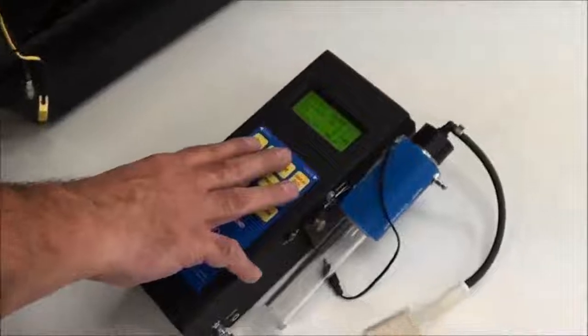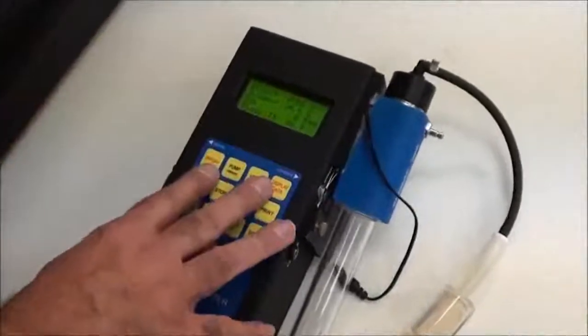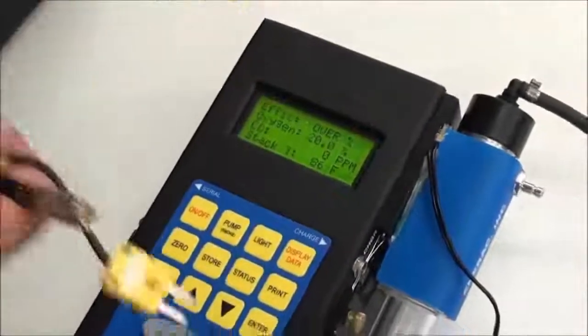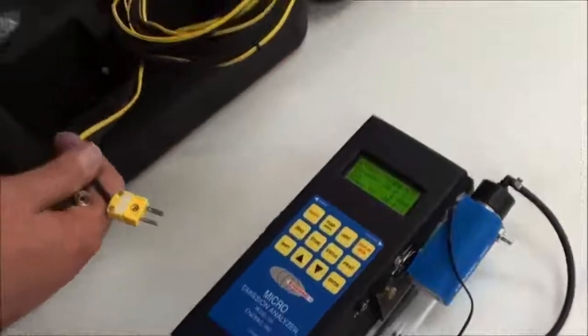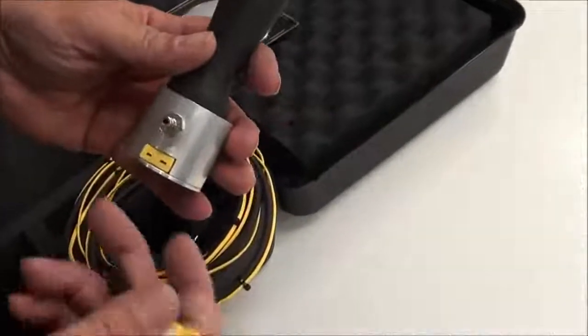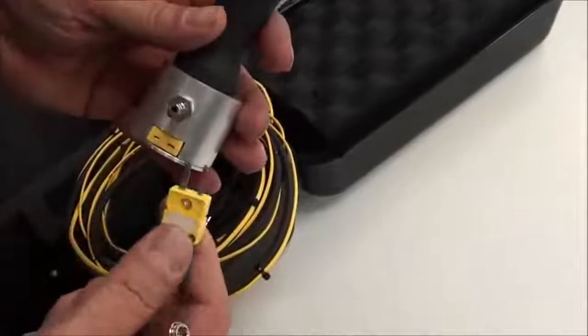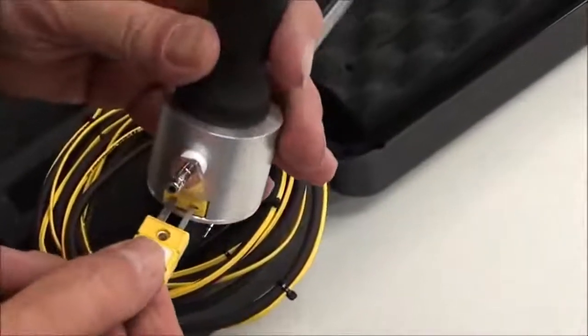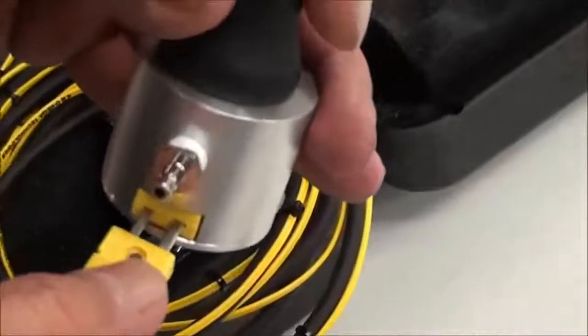When we ship it from the factory, it comes with rechargeable batteries installed, and the switch is always in the on position. So if you happen to use alkalines in the field and flip that switch down, when you go back to the rechargeables, don't forget to flip that switch back to the on position. I always recommend turning the unit on first. As soon as you take it out of the case, turn it on. This gives the sensors a chance to stabilize a little more. Then make your connections. You have the probe connection, the thermocouple, and the gas fitting. The thermocouple plugs in. It's keyed, so you can only put it in one way.